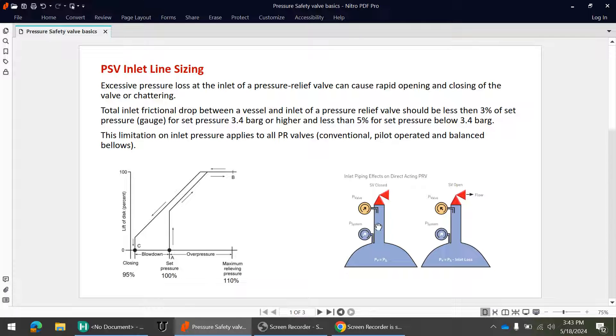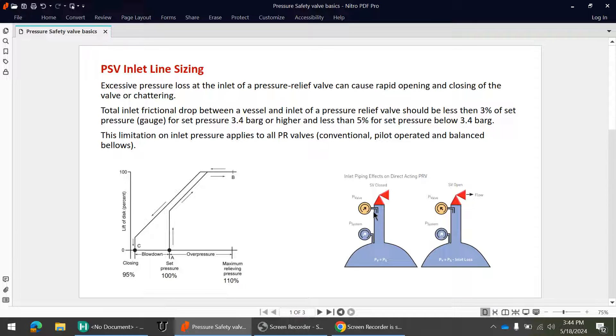In this diagram you can see how the inlet line loss causes the chattering issue. In the first diagram there is a vessel, and Pv equals Ps — Pv is the vessel pressure and Ps is the set pressure of the PSV. At the PSV inlet, the gauge shows pressure just before the PSV opens, so there is no flow and the vessel pressure and PSV inlet pressure are the same.